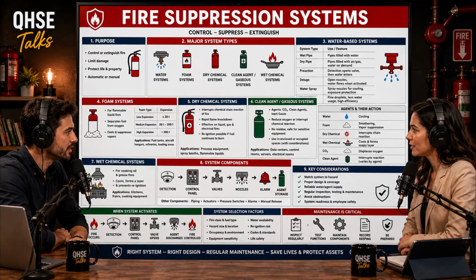It takes a vastly larger fire to eventually fill up that entire upper space and push the hot air down to the sprinkler head. That is a phenomenal example of how minor, seemingly harmless facility maintenance issues, like leaving a few ceiling tiles out, can completely cripple a $1 million engineered safety system. Precisely. You can design the best system in the world, but if the facility geometry changes, the system fails.